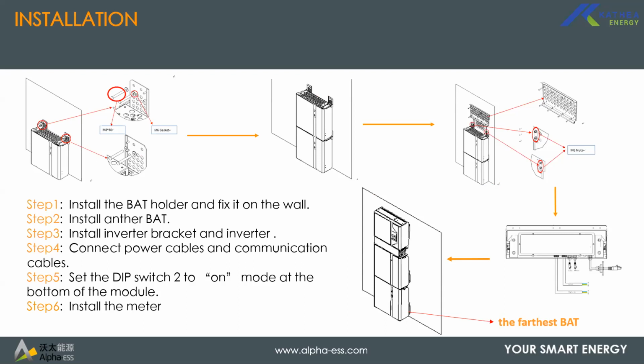You need to set DIP switch number 2 on. You can access this DIP switch port when you open the battery cover. There is a small plate there with 2 screws. So if you just unscrew that plate, on the inside there are 4 DIP switches there. Then you would need to set the last battery DIP switch number 2 to on. This basically notifies the BMS daisy chain that this is the end of termination for the batteries.